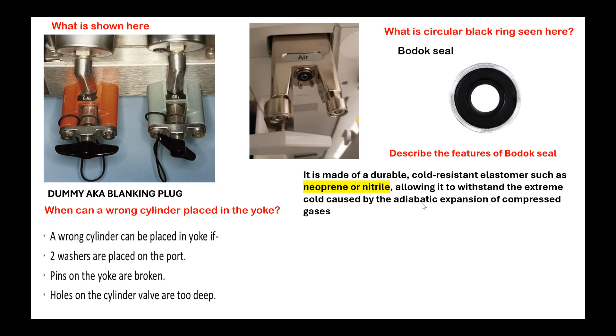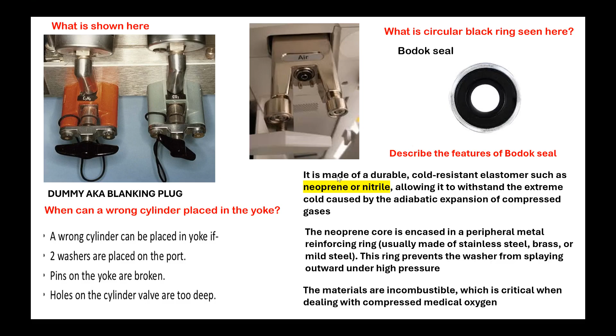The neoprene core is encased in a peripheral metal reinforcing ring. This white thing is the metal ring, usually made of stainless steel, brass or mild steel, and this ring prevents the washer from splaying outward under high pressure. So that is how it prevents. And the materials are incombustible, they don't burn. This is very critical when dealing with compressed medical oxygen. So steel cannot be burned.